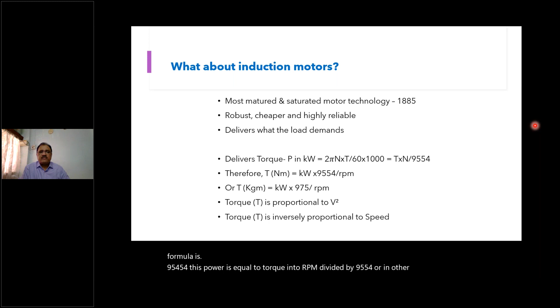You must be familiar with this formula. Kilowatt is equal to 2 pi NT divided by 60,000. So the short form or simplified formula is power is equal to torque into RPM divided by 9554. Or in other words, torque is equal to 9554 into kilowatt divided by RPM.